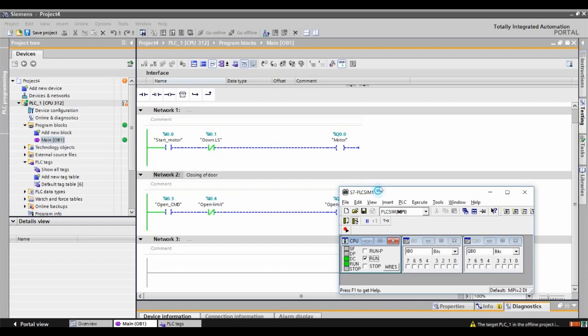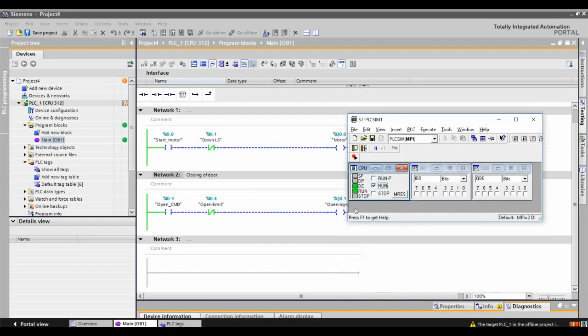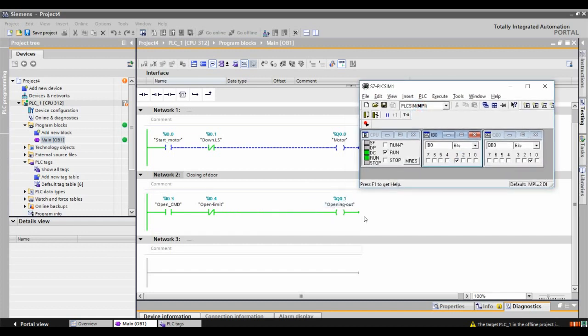Now we will see the opening sequence of the garage door. We have i0.3 as the open command in the simulator. When I press i0.3, the output q0.1 activates — that is for opening the door. The motor, which was previously in forward position, now moves in reverse to open the door. It will continue opening until it touches the open limit. We have i0.4 as the open limit.